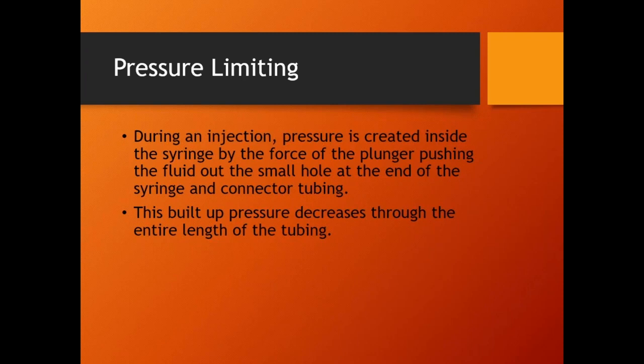Now, they might have to do the injection again anyway. I mean, if we're asking for an injection of 8 milliliters per second and it had to go down to 2 milliliters per second, yeah, something's wrong. That's probably not going to be enough fluid to give us the image we need. But if it goes from 8 milliliters to 7.7 milliliters per second, yeah, pressure's limited, but we're still good. So that's why they don't want to stop the injection, because then it's an added patient dose that didn't necessarily need to occur. That's not universally true, but most models do follow that procedure. If we hit a pressure limit, we'll just slow the injection down to the maximum flow we can do at the selected maximum pressure.